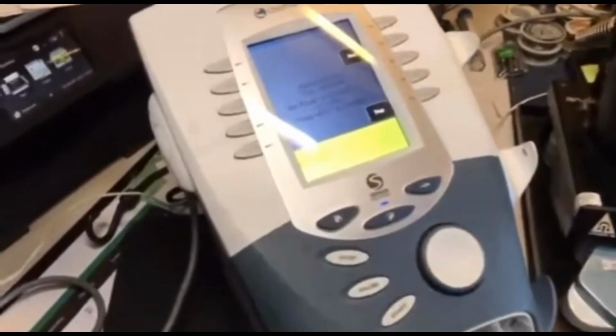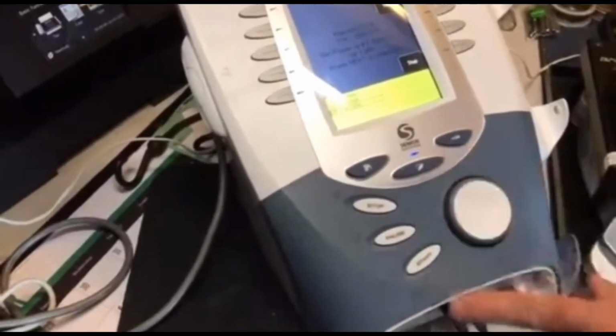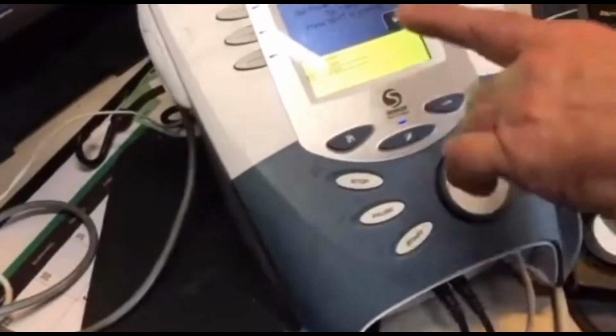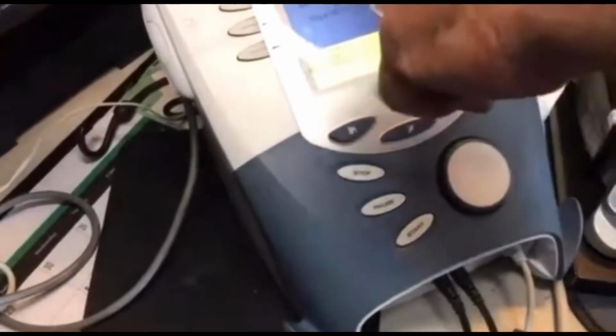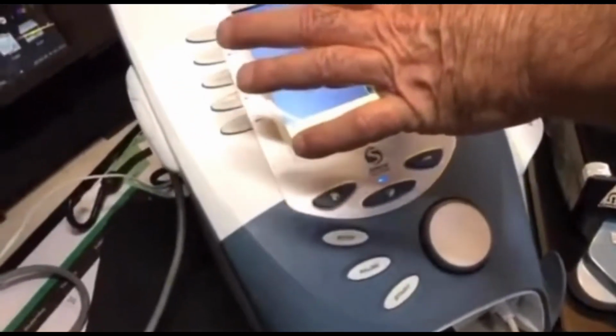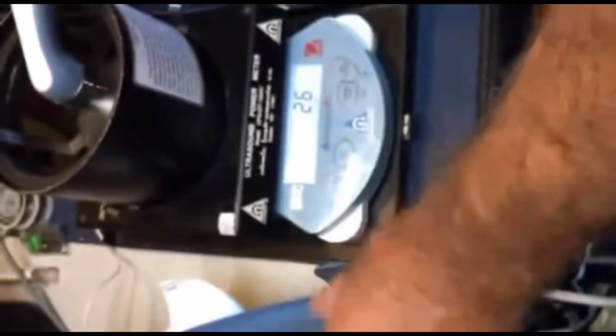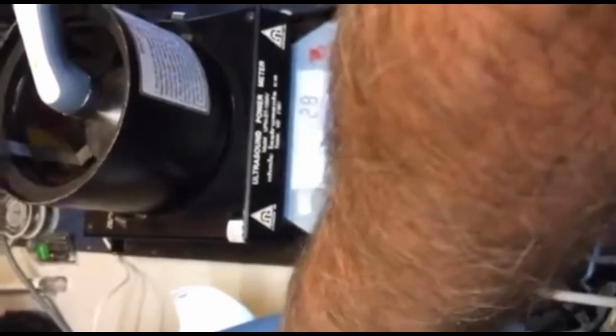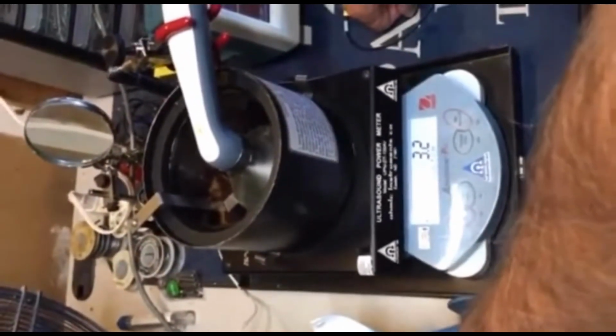Well, that's good. So now it's telling you to set your meter to 4 watts. What most people do is start spinning the dial or looking at the machine, expecting it to show wattage. No, pay attention to your meter. As you're ramping it up, you'll notice this starts going up as soon as the meter reaches 4 watts. It comes up quickly too, usually right up around 300 something. That's where you'll start seeing it get close. And if you spin it too quick, you'll miss it, and it's kind of a pain to have to go back.